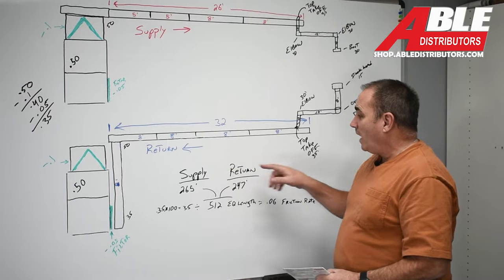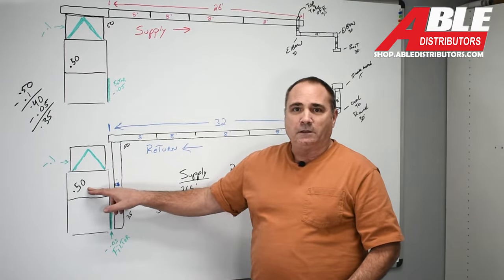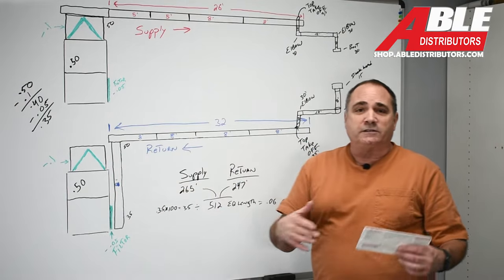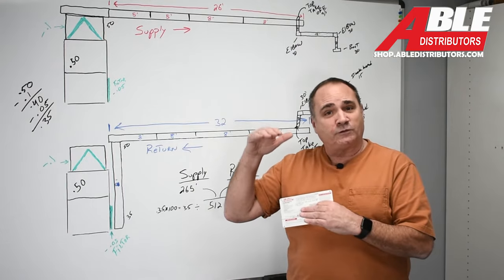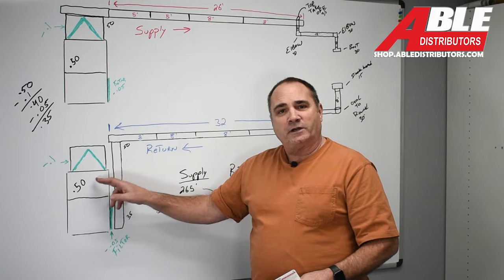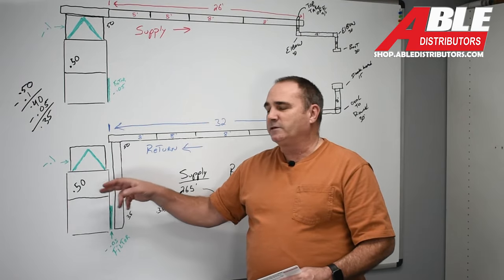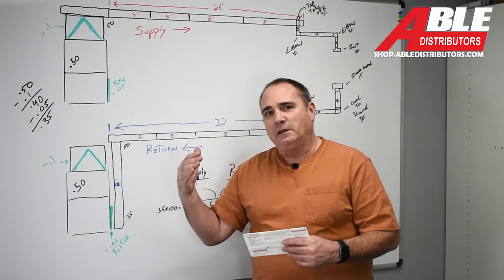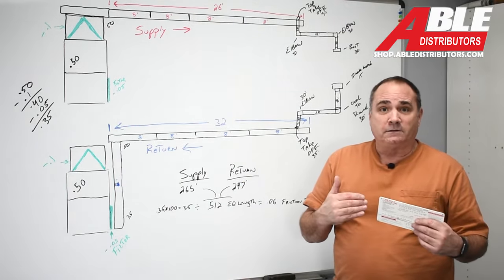Now, you may find that a 0.5, you're just not going to be able to do it. And in most furnaces, there's a little guide. It'll tell you how many CFMs you're going to get at 0.5, which would be perfect for them. But they'll go 0.6, 0.7, and you might find that you have to take that furnace and kick it on to a higher speed to get the desired CFM that you're going to want.